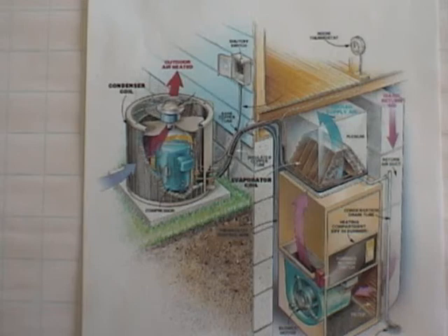So these units typically for residential are rated at a 1/2 inch of static pressure, which gives you a quarter, 0.25 on the suction side and 0.25 on the discharge side. It's not unusual to find these units installed with restrictive return and restrictive supply and up to 1 inch of total external static pressure.